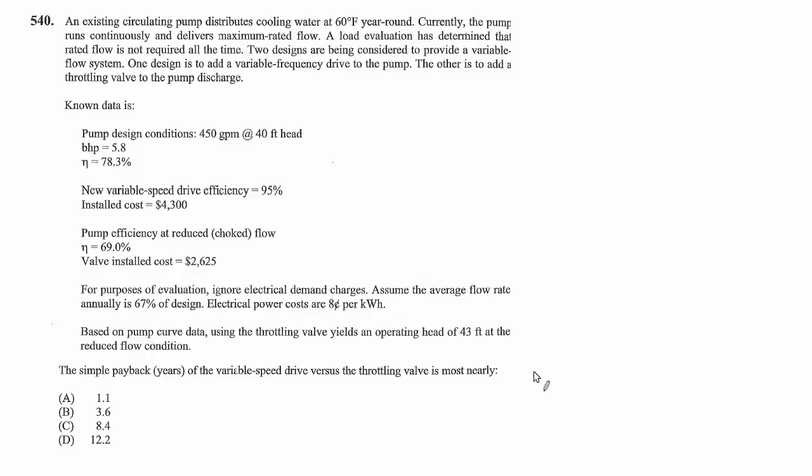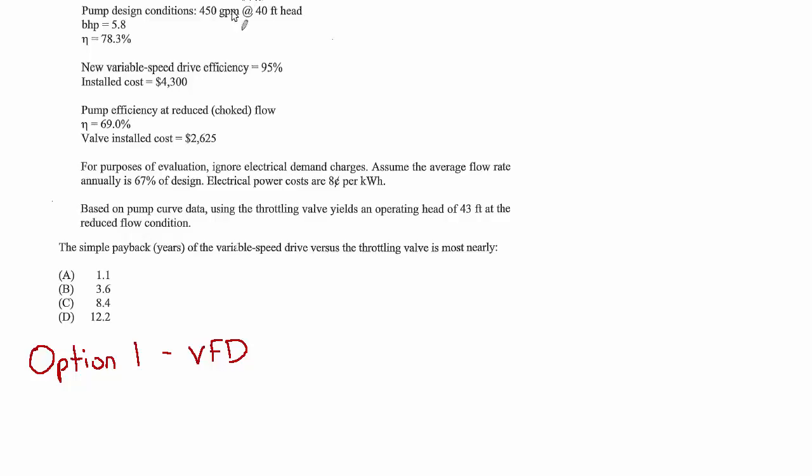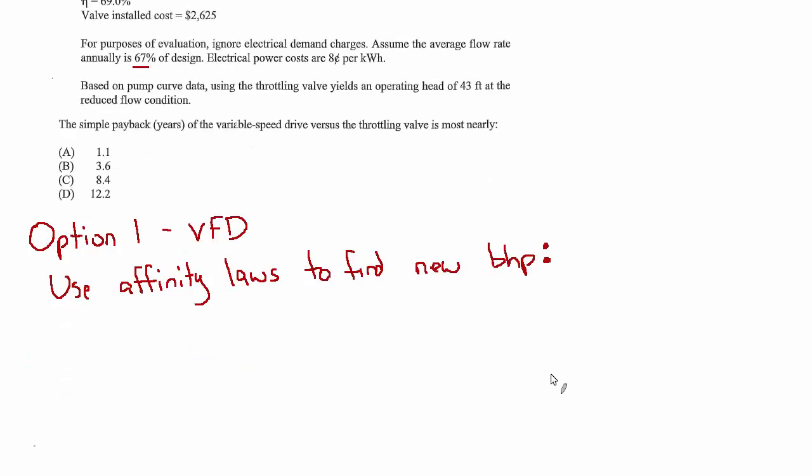Let's start with option one for the VFD. Since we know the flow rate design is 450 and it's going at full flow, we only need to run at 67% of that. And at full flow, the brake horsepower is 5.8. So we can use the affinity laws to find the new brake horsepower. The power changes with the cube of the flow rate or the speed. So we can say BHP2, or the new BHP, as compared to BHP1, will be Q2 over Q1 cubed.